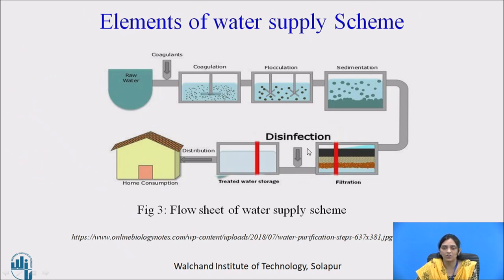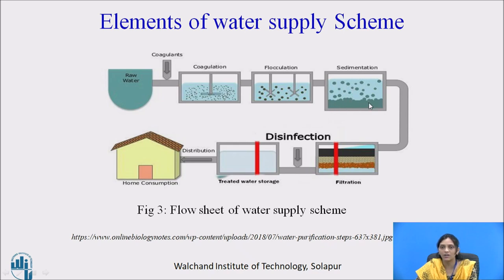This is an alternate flow chart of the water treatment plant, making it more clear what flocculation and sedimentation are. There is raw water; after screening and aeration, a coagulant agent is added to the water. After addition of the coagulant agent, floc formation begins. The black dots shown represent the floc formation — all the small dust particles stick together and form large, heavy particles. This process is called flocculation. Then those heavy particles have to settle down at the bottom, so the water is sent into the sedimentation tank, where all the heavy particles settle at the bottom.